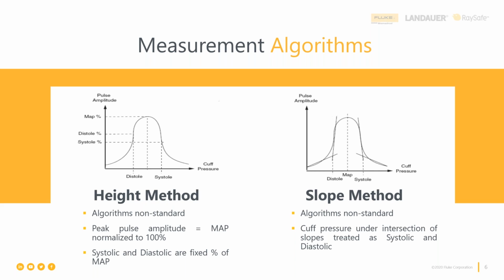The slope method, which has been used for a long time in a lot of different automated devices, is really more of a calculus way of doing things. So it's using a series of point slope measurements in order to come up with what is the systolic and what is the diastolic measurement value. Once again, the peak pressure in the cuff is assumed to be the mean arterial pressure. And then systolic and diastolic pressures are calculated, in this case using calculus, a point slope way of assessing what the systolic and diastolic pressures are compared to the mean arterial pressure. So at a high level, that gives you a little bit of an understanding of what's going on. Once again, it's not disclosed specifically or dealt with specifically by any manufacturer that I have seen or that I know of.